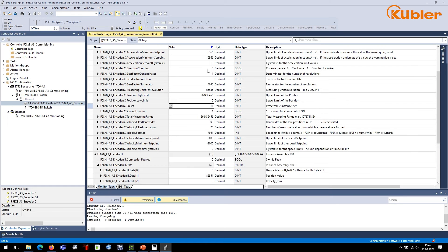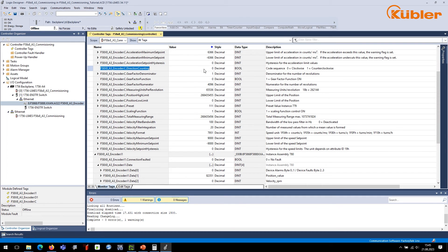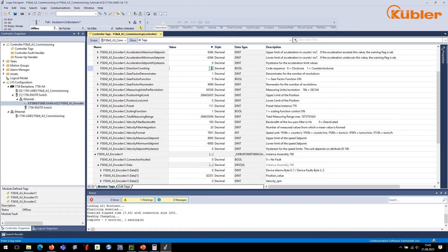The counting direction can be configured in the exact same way. Go offline and navigate to the parameter direction counting. Note the actual value. Value 0 indicates the direction clockwise. Value 1 is to be set for a counterclockwise direction. In this example, we set the counting direction to counterclockwise, which means it is set to 1.